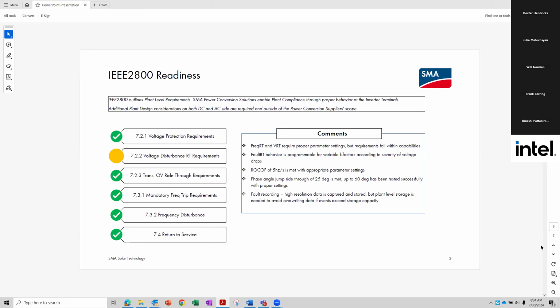The frequency trip requirements in section 7.3 haven't really changed that much. Our present products and future products will all meet the frequency trip requirements. Same is the case with frequency disturbance. Typically, frequency is not generally the problem for inverter behavior. So the 7.3.2 section is also fairly easily met. And then the return to service section 7.4, again, SMA can comply with those requirements.